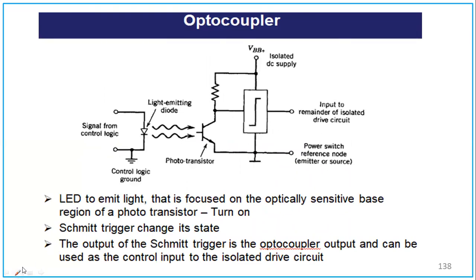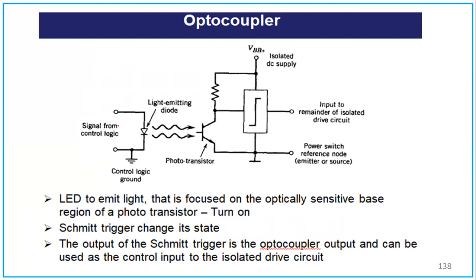For the optocoupler isolation method, a signal from logic control is fed to a light-emitting diode which emits light focused on the optically sensitive base of a phototransistor. This turns on the phototransistor, which in turn provides the gate pulse. A Schmitt trigger changes its state based on the optocoupler output, and that output is used as the control input to the isolated drive circuit, which has its own isolated DC supply.